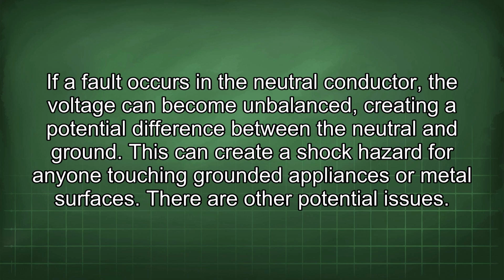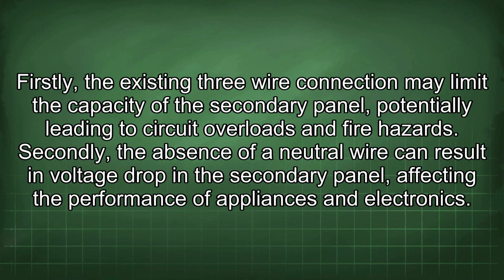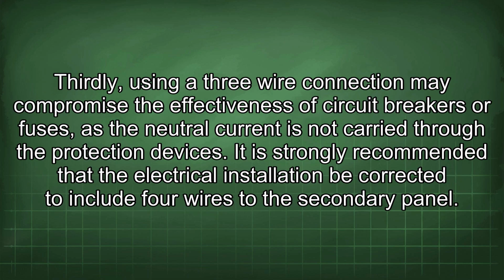There are other potential issues. Firstly, the existing 3-wire connection may limit the capacity of the secondary panel, potentially leading to circuit overloads and fire hazards. Secondly, the absence of a neutral wire can result in voltage drop in the secondary panel, affecting the performance of appliances and electronics. Thirdly, using a 3-wire connection may compromise the effectiveness of circuit breakers or fuses, as the neutral current is not carried through the protection devices.